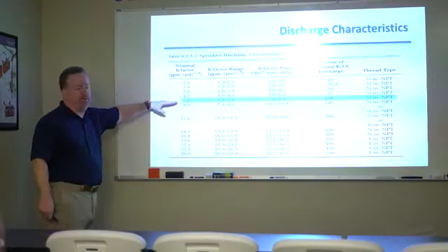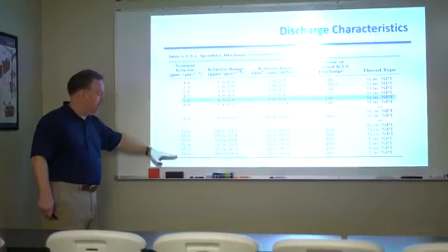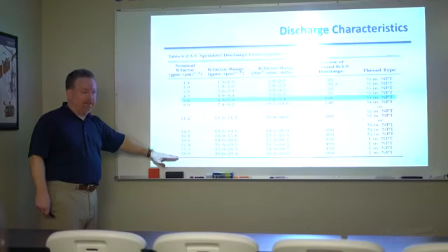So if we had a K5.6 sprinkler that was capable of spraying 20 gallons per minute, how much can a K28? Yeah, 100 gallons a minute. That's a little hose stream up there.